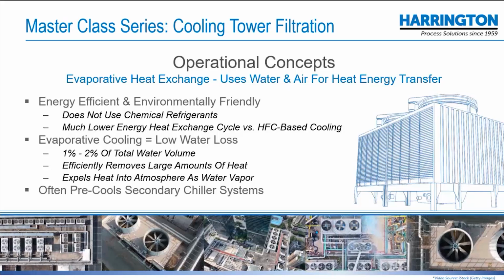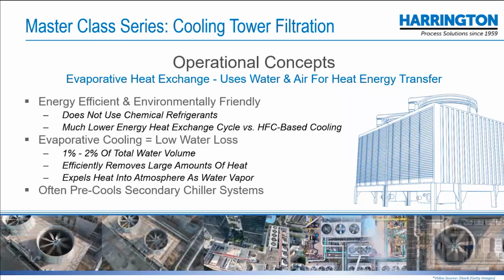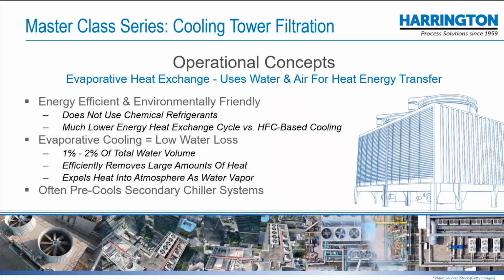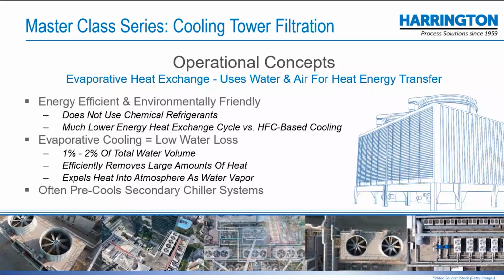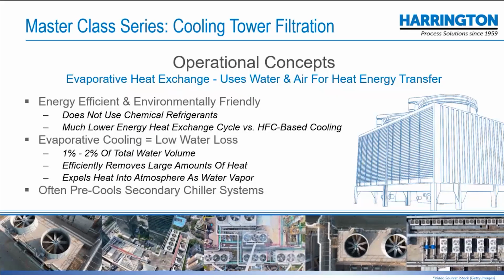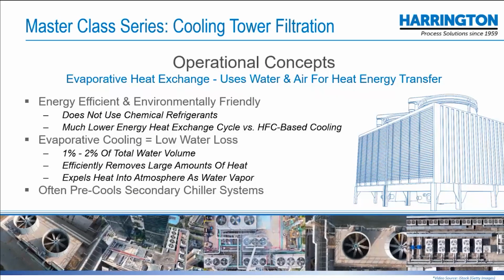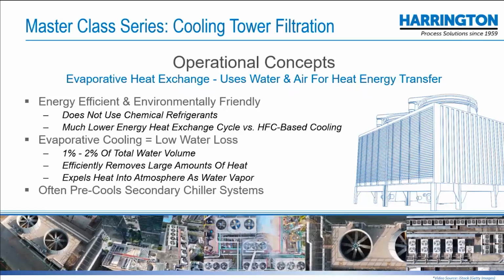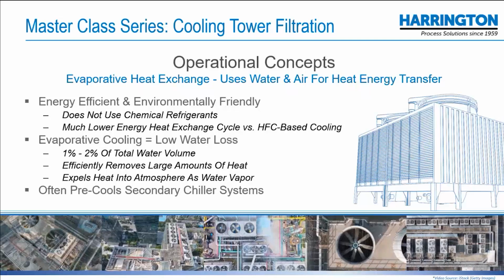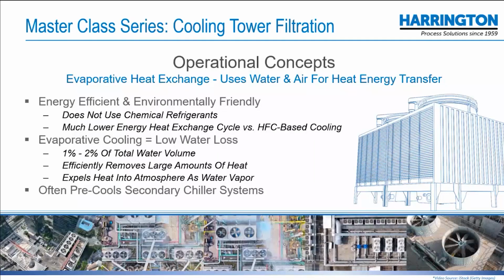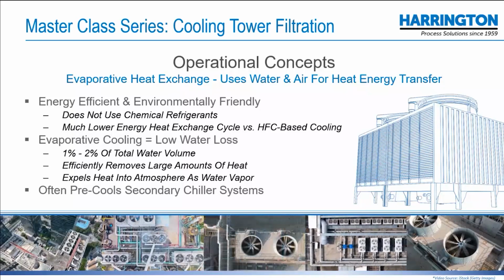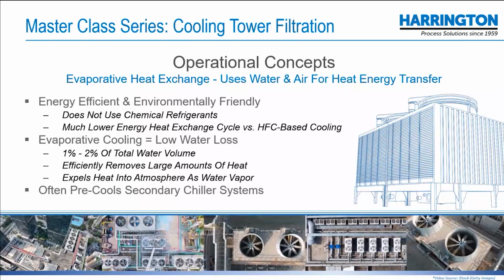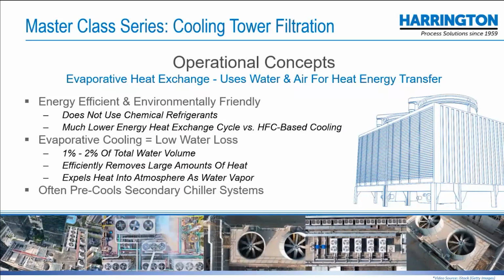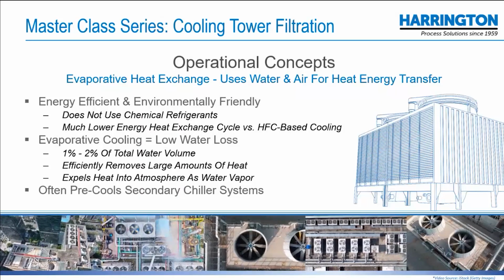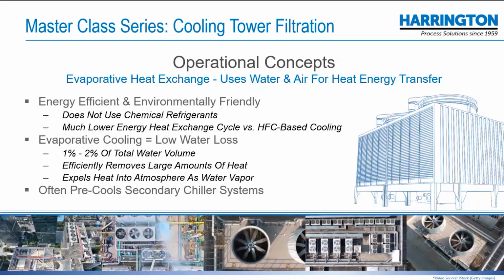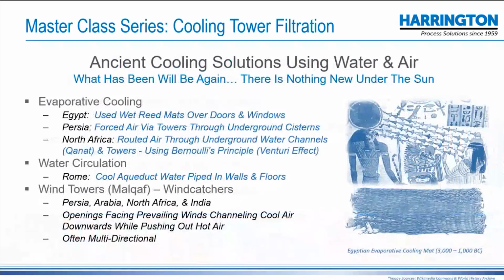It's mostly due to a term that's called blowdown. Basically, as solids and dirt collect in the reservoir of the cooling tower, they have to be purged from the system. And so there's a wastewater loss associated with cooling towers that far exceeds this 1 to 2%. It expels heat into the atmosphere as water vapor, and it's often a first step to a cooling process that may be followed by secondary chiller systems that could be chemical refrigerant based. But they're used both for HVAC and for process water within facilities, and we'll see more about that in the next slides. But the first thing is to understand that evaporative cooling as a technology is nothing new.